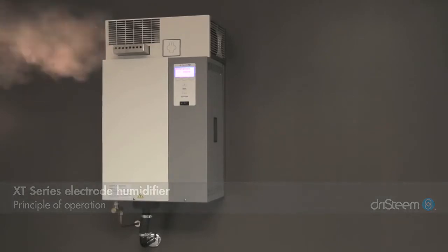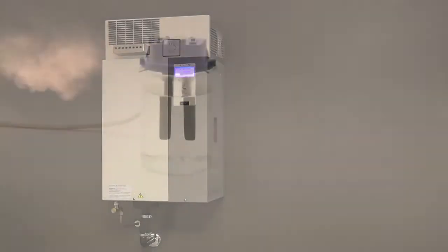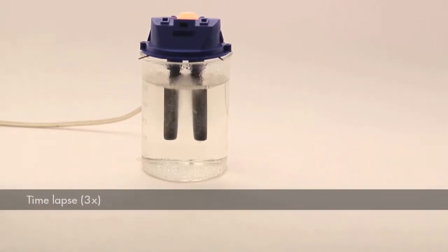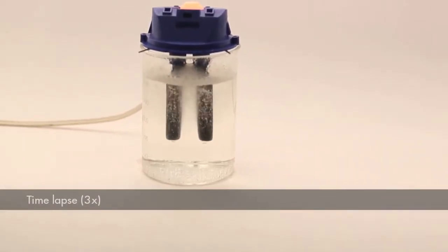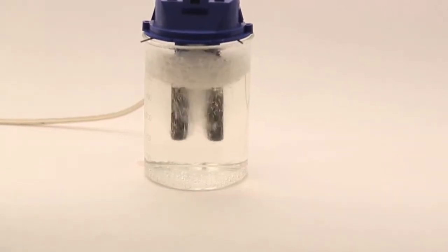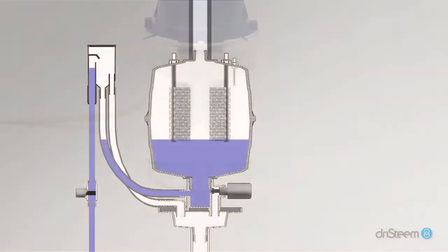DriSteem XT series electrode steam humidifiers operate on the principle that electrical current in conductive water causes heat. Enough current between submerged electrodes in conductive water causes enough heat to boil the water into steam, and it works very predictably.